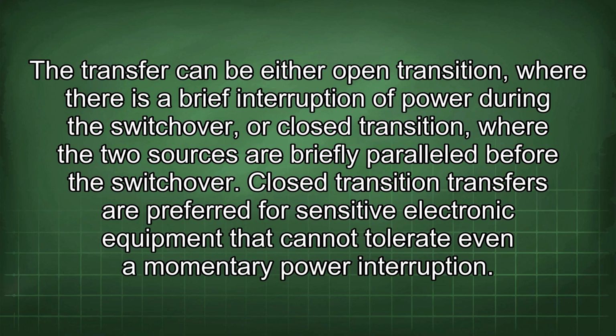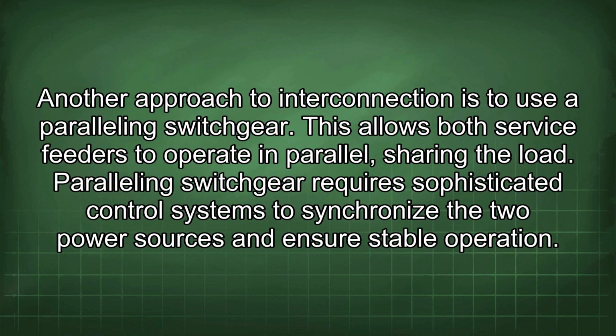The transfer can be either open transition, where there is a brief interruption of power during the switchover, or closed transition, where the two sources are briefly parallel before the switchover. Closed transition transfers are preferred for sensitive electronic equipment that cannot tolerate even a momentary power interruption. Another approach to interconnection is to use a paralleling switchgear. This allows both service feeders to operate in parallel, sharing the load. Paralleling switchgear requires sophisticated control systems to synchronize the two power sources and ensure stable operation.